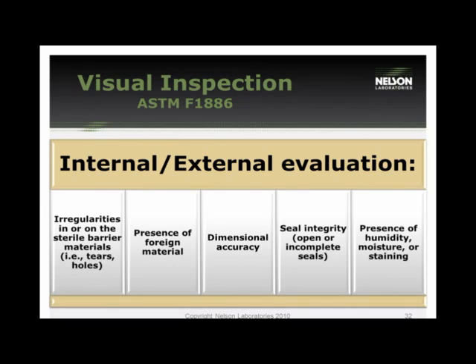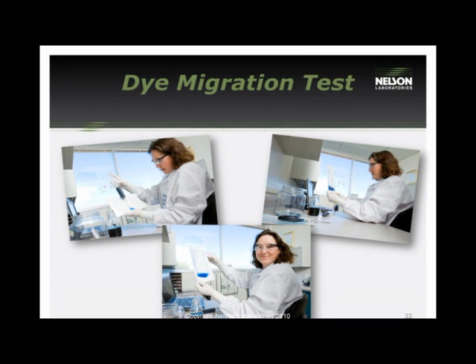Moving into integrity tests, the most common is visual inspection, regulated by F1886, involving both internal and external evaluations of the materials. You are looking for irregularities such as tears, holes, any foreign materials, and seal integrity — whether it is open or incomplete — as well as any humidity, moisture, or staining concerns. Finally, you can use it to define the dimensional accuracy of the width of the seals.